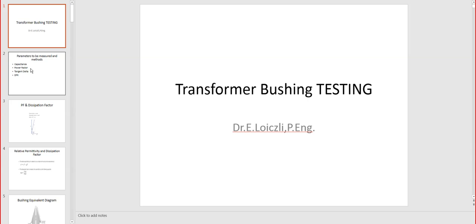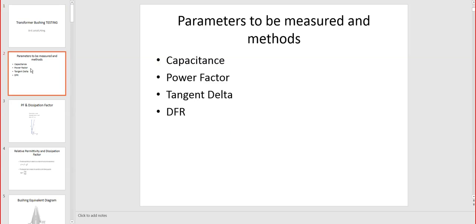What we're going to cover here is some testing that was done on the MOT, and we will explain what they mean. So typical testing for the bushing are capacitance testing, power factor testing, tangent delta, and dielectric frequency response. Those are the four types of testing that we actually do, and they are interrelated. We're going to see how.